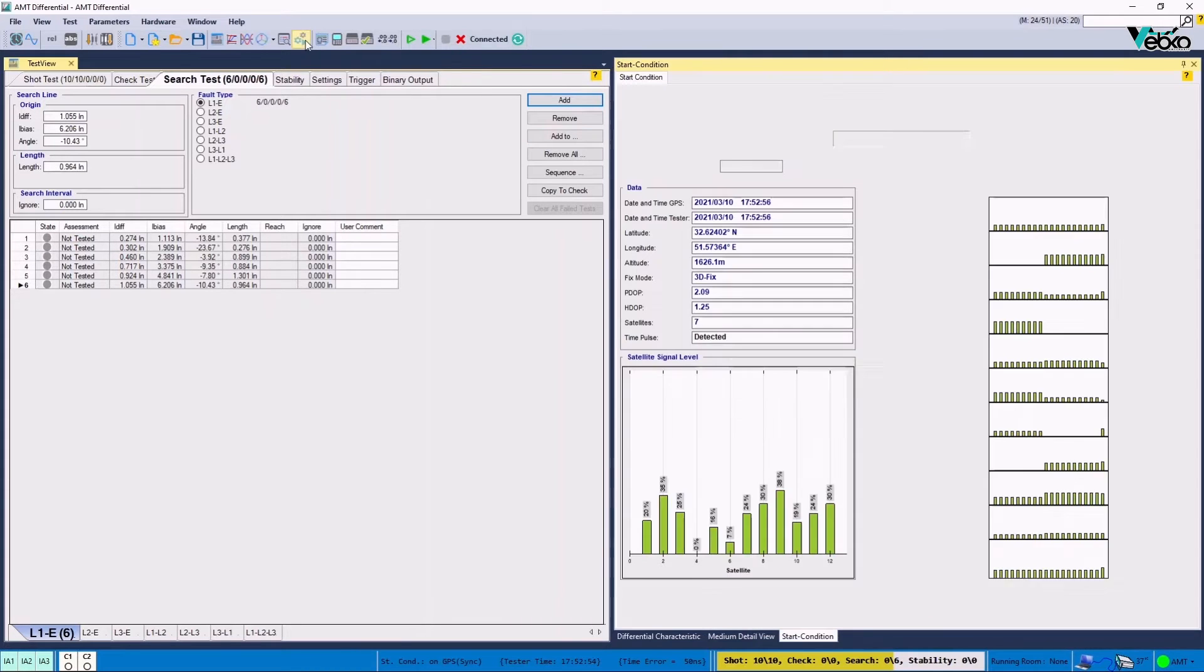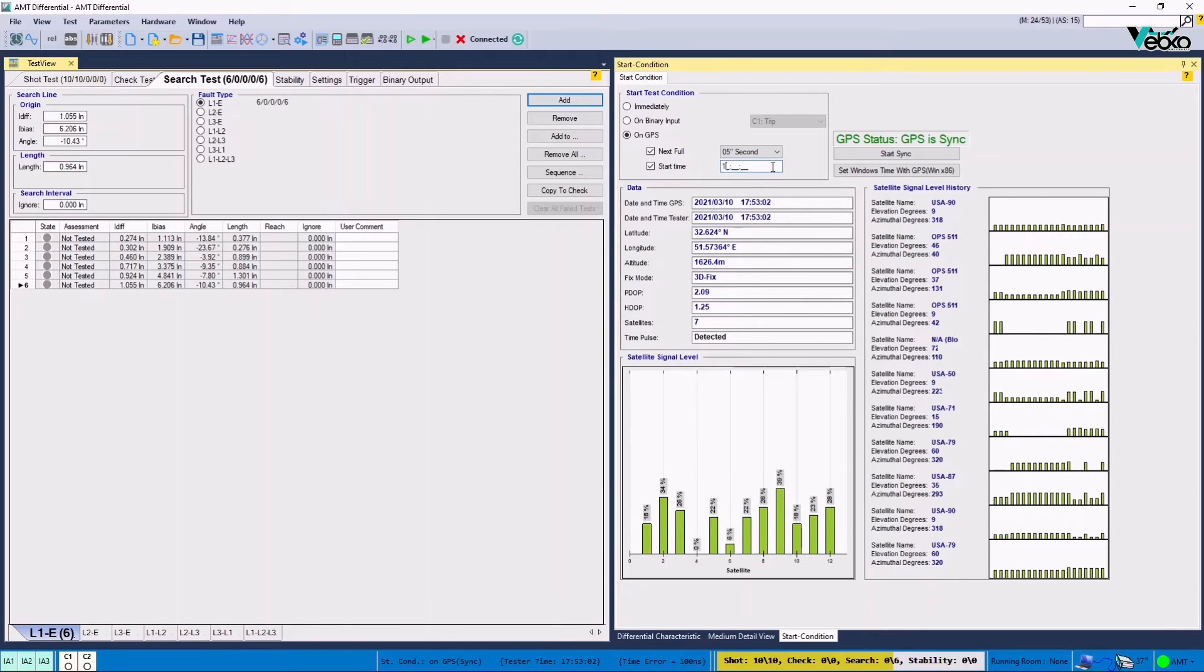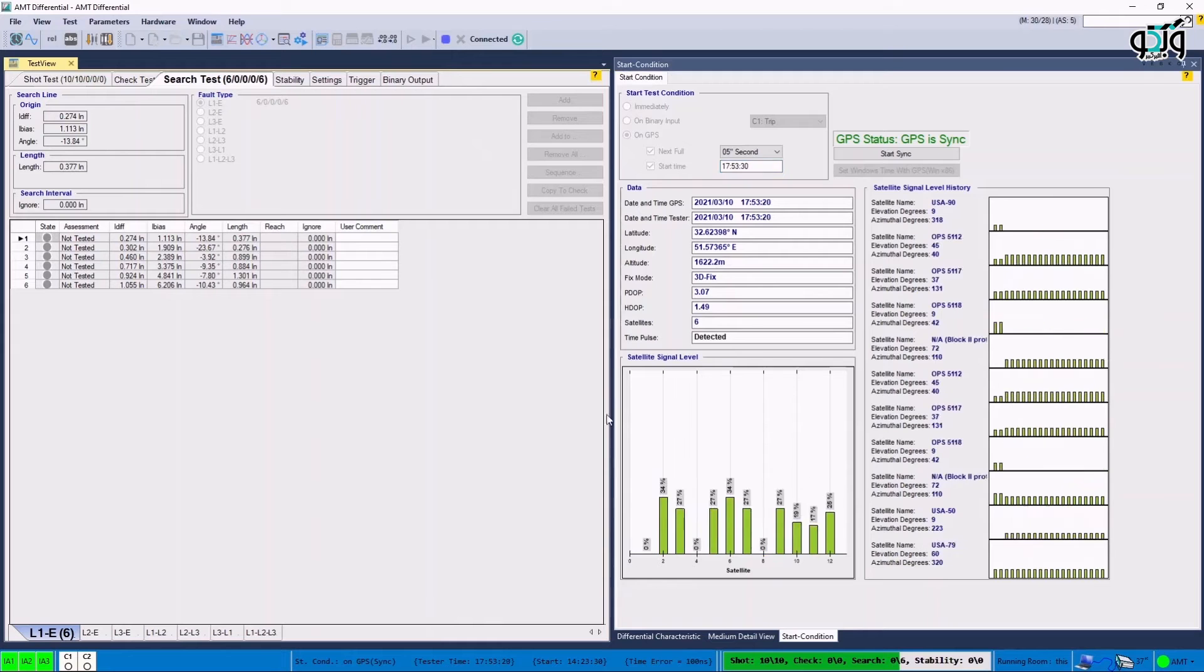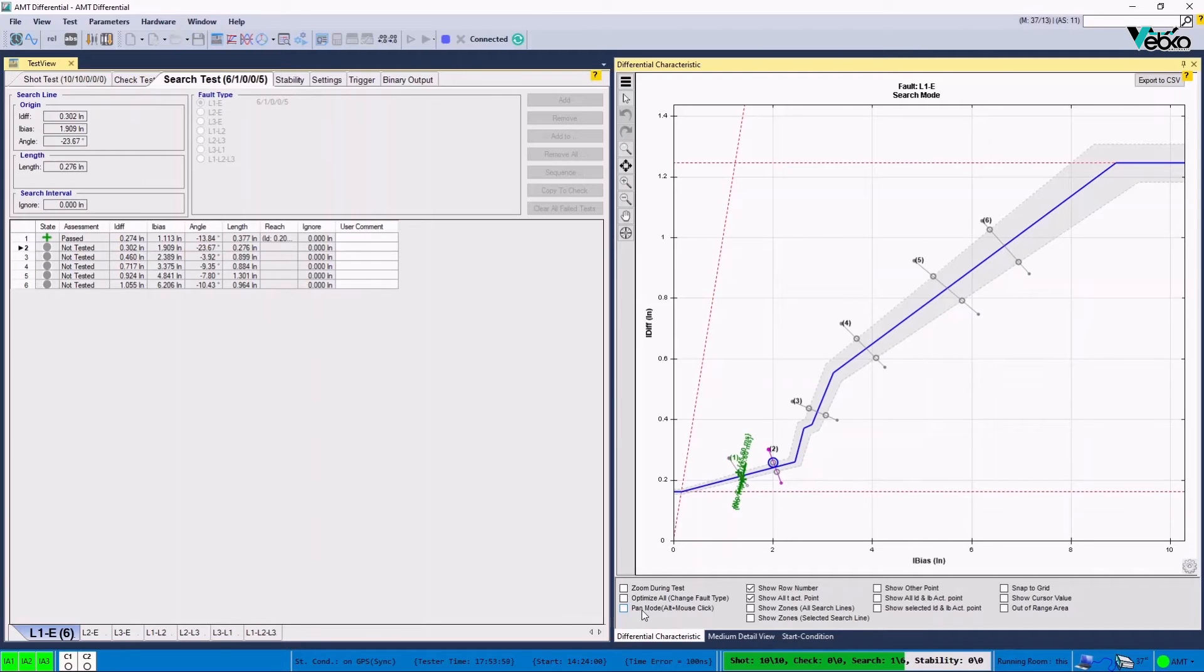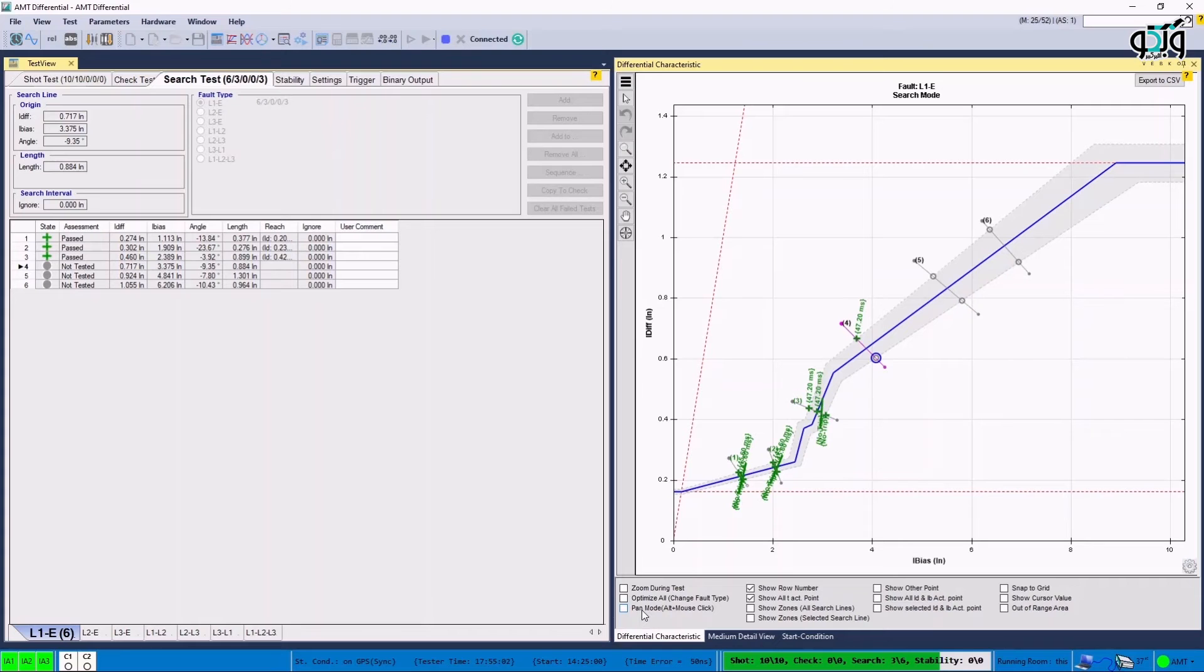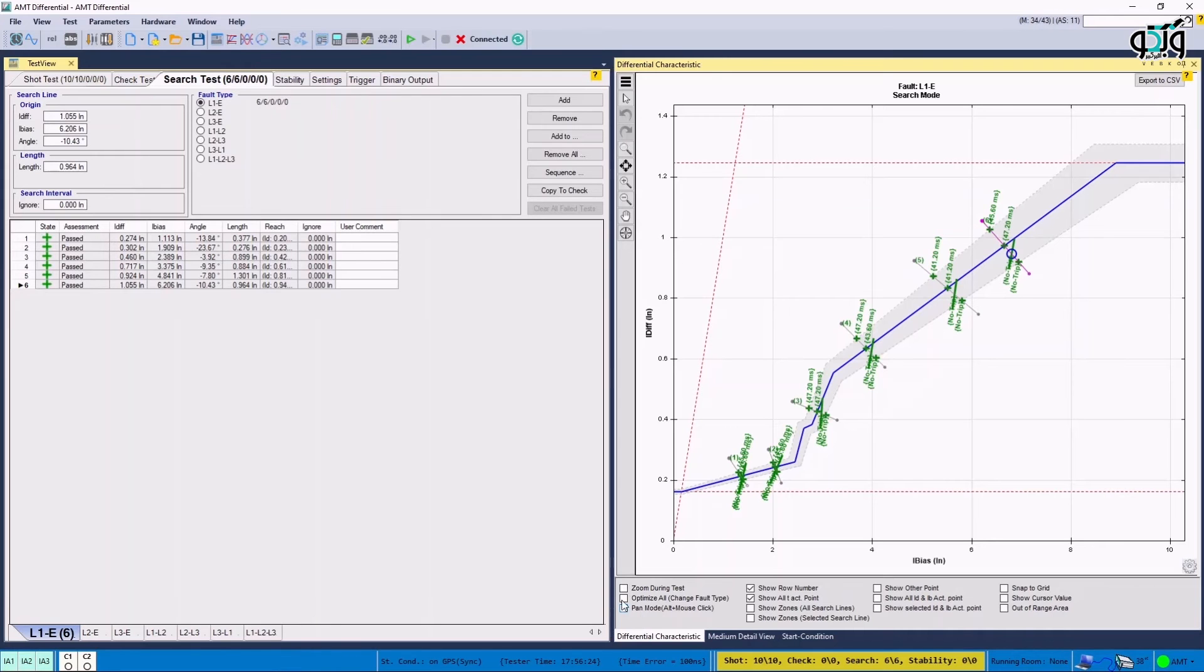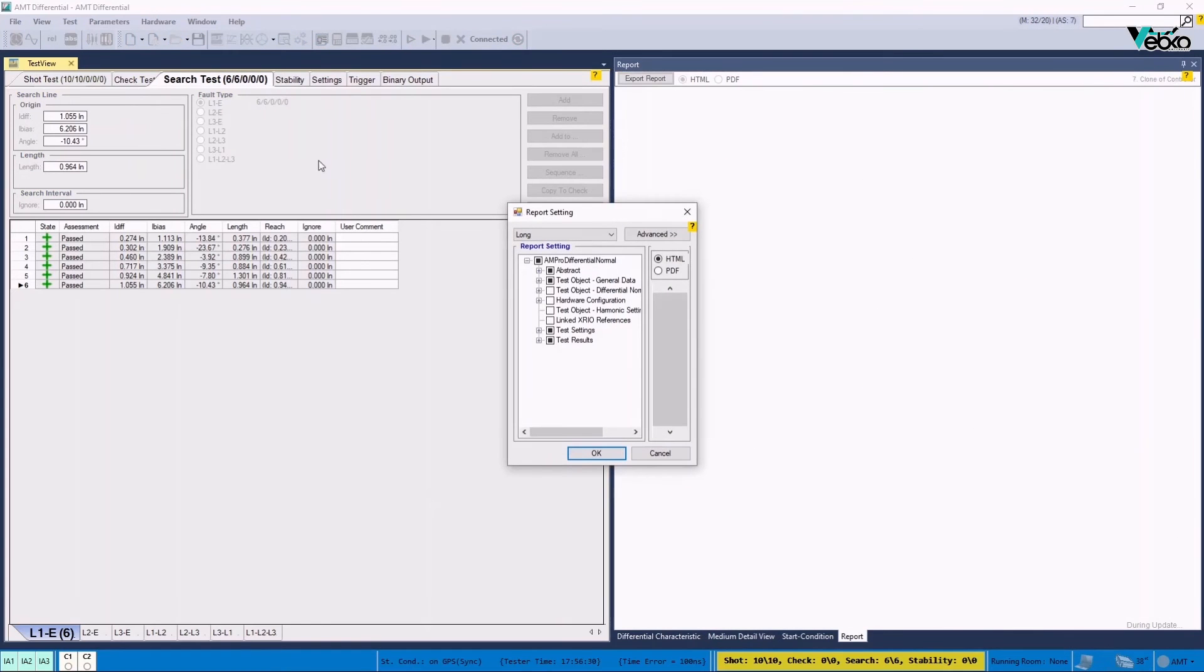After drawing the search line and adjusting the setting in start condition window, by starting the test, the software starts interpolating the characteristic curve by testing several points on the search line and then determines the exact location of the characteristic curve.